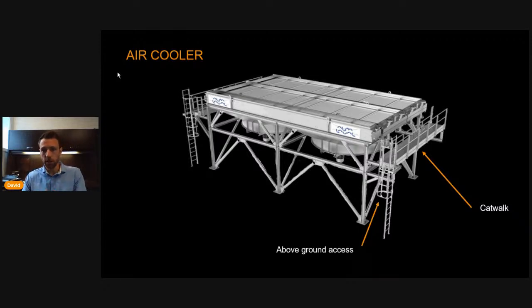So it's reduced, limited space. Once you open up the first tube, you don't have direct access to the tubes themselves - there's the header box. The header box is an empty region where the fluid gets transferred. It's about 8 to sometimes 16 inches, varies in length, but the tubes don't start there already - you need to pass through the header box to access the tubes.